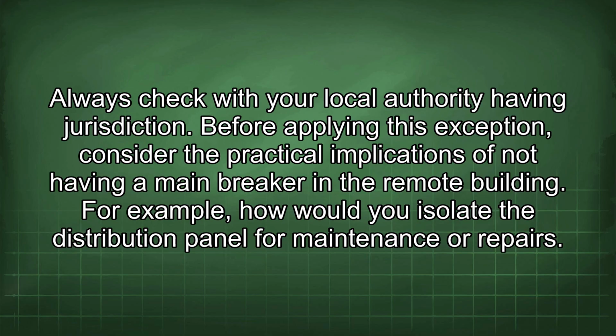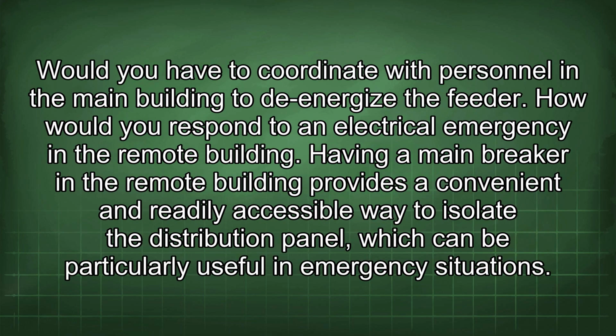Before applying this exception, consider the practical implications of not having a main breaker in the remote building. For example, how would you isolate the distribution panel for maintenance or repairs? Would you have to coordinate with personnel in the main building to de-energize the feeder? How would you respond to an electrical emergency in the remote building? Having a main breaker in the remote building provides a convenient and readily accessible way to isolate the distribution panel, which can be particularly useful in emergency situations.